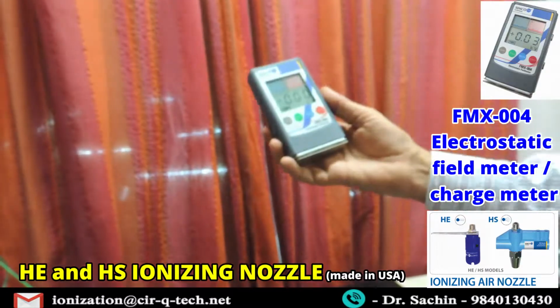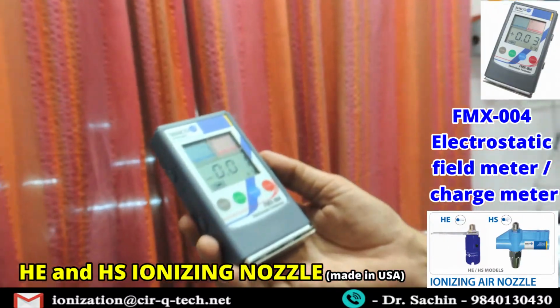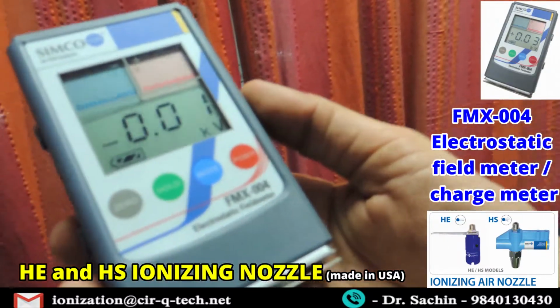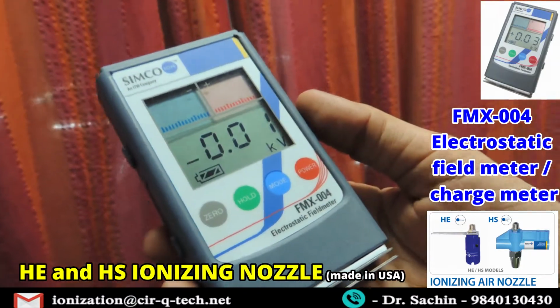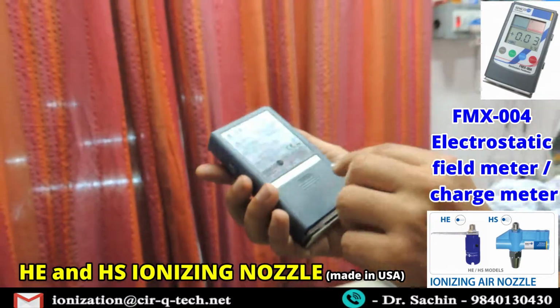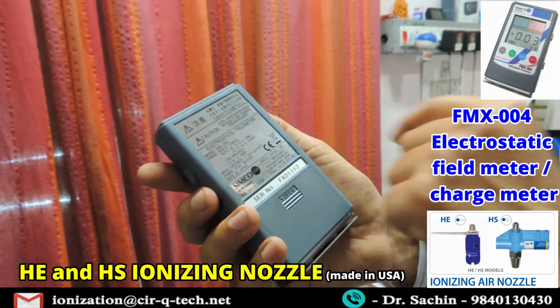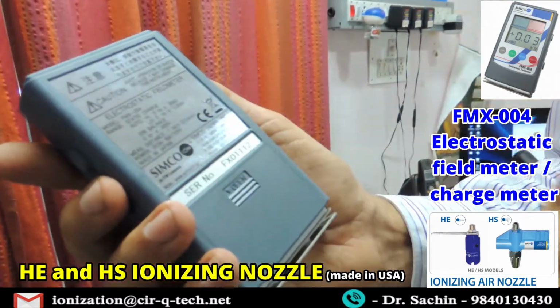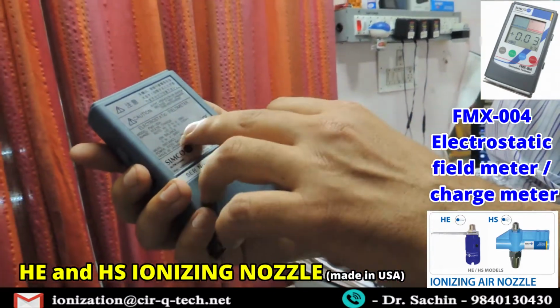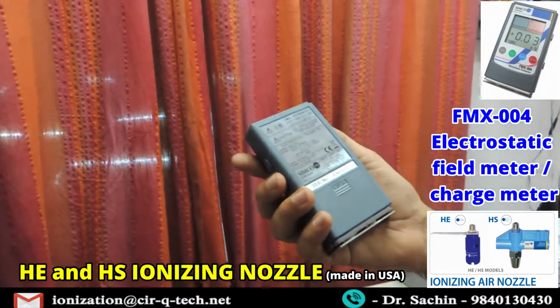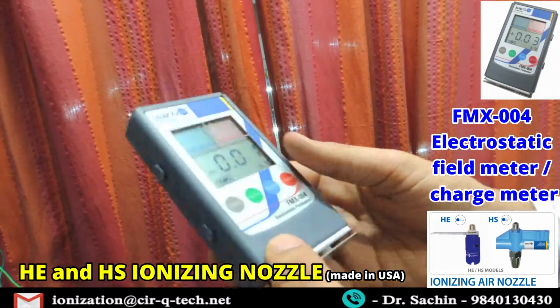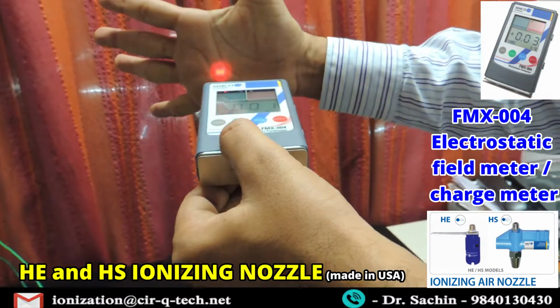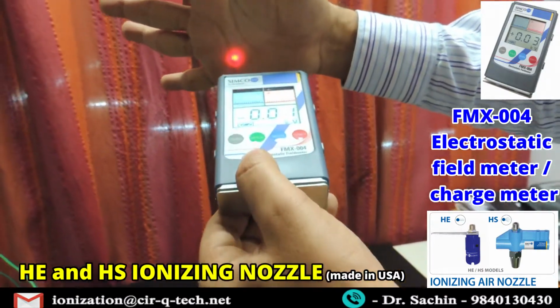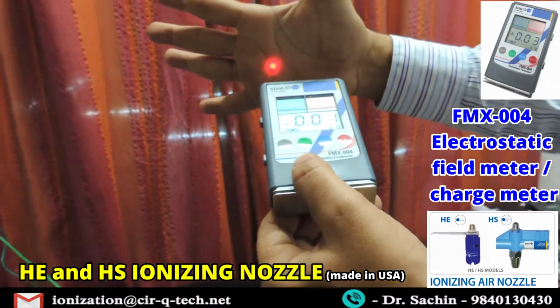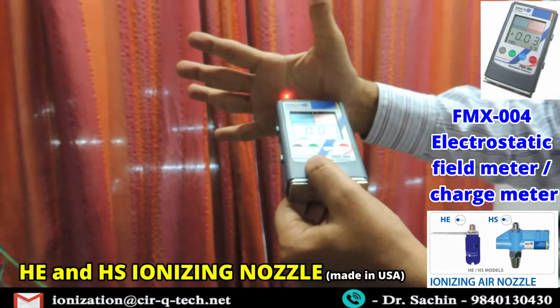I'll be using an electrostatic field meter. The latest one from Simco is the FMX004. It has a very high range. It can measure up to plus or minus 30 kV, with a low range of 3 kV, and ion balance up to plus or minus 300 volts. A simple device which you just press, and wherever these two lights meet, you should be able to take a reading. You should not be too far, you should not be too close.